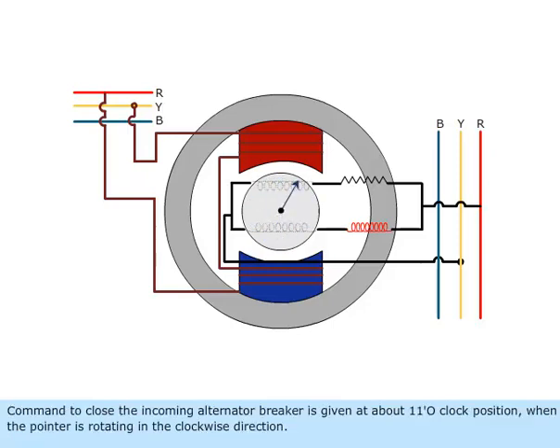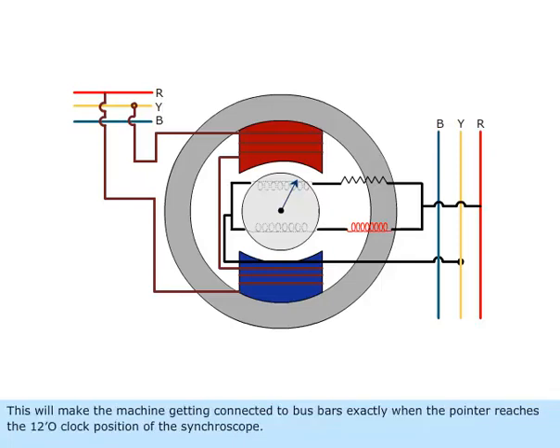Command to close the incoming alternator breaker is given at about 11 o'clock position when the pointer is rotating in the clockwise direction. This will make the machine getting connected to bus bars exactly when the pointer reaches the 12 o'clock position of the synchroscope.